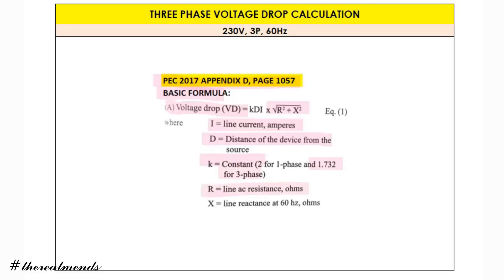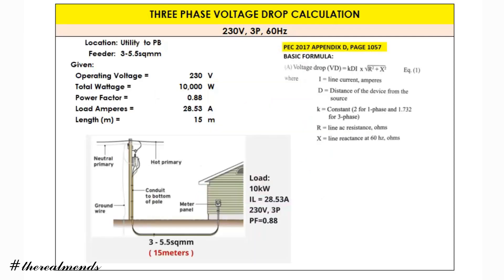R is the line resistance in ohms, and X is the line reactance at 60 hertz expressed in ohms. Now let's use this formula to solve for the three-phase voltage drop calculation. Our given values are: operating voltage 230 volts, total wattage 10,000 watts or 10 kilowatts, power factor 0.88, and load amperes 28.53.